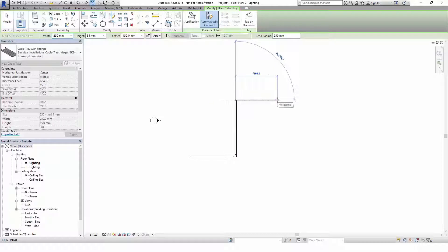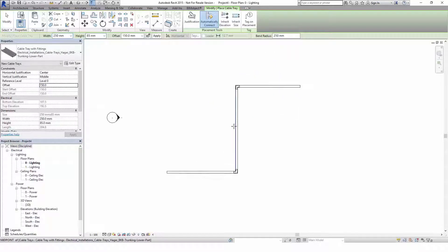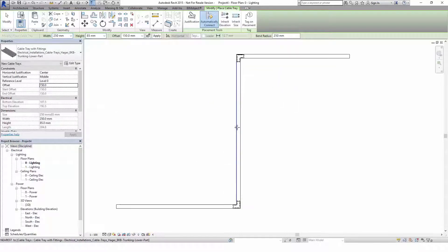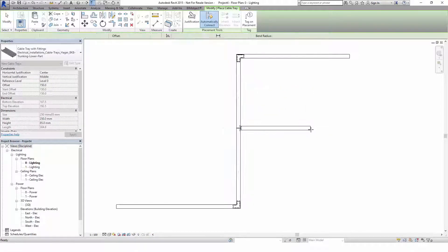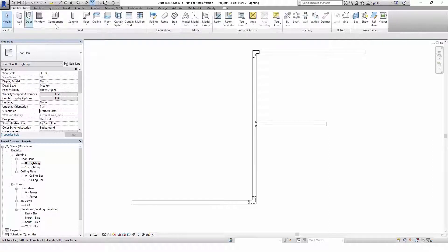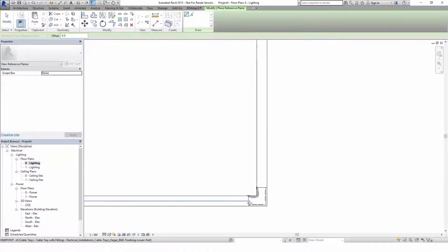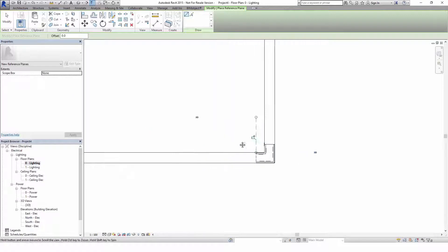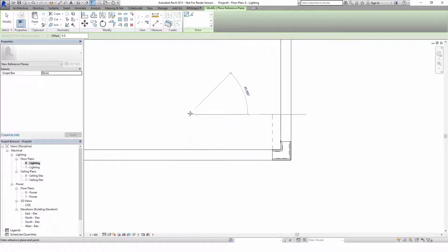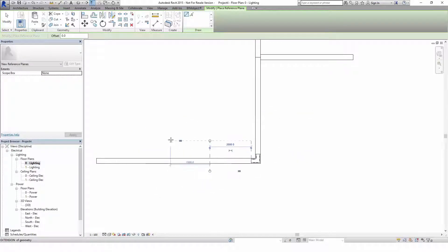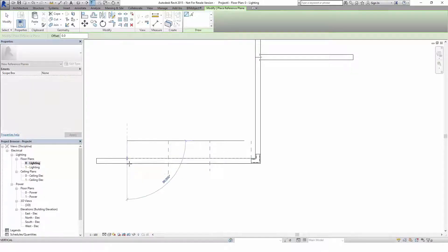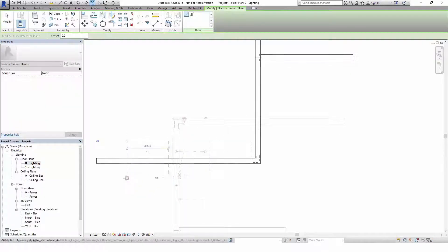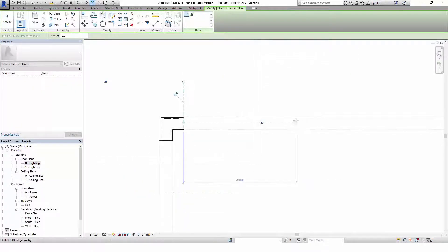By creating a 90 degree corner the system automatically places an elbow element. As mentioned before the length of one selling unit is 2 meters, so we recommend that you draw reference planes every 2 meters. This way Revit will be able to calculate the correct number of required pieces for your project.